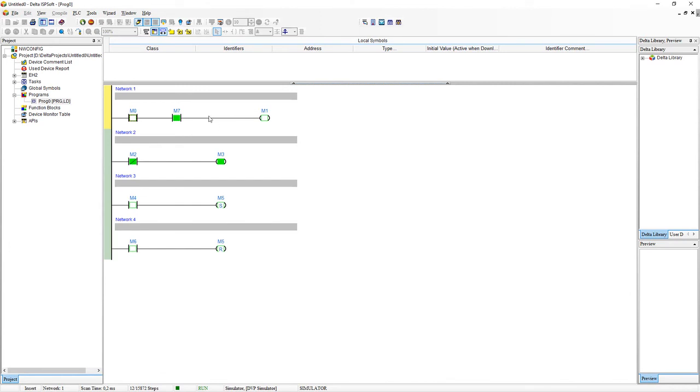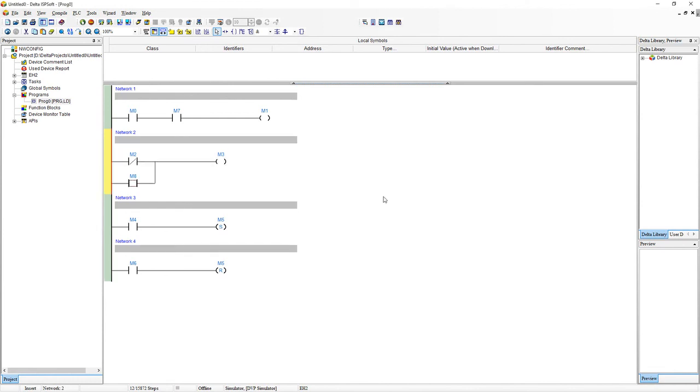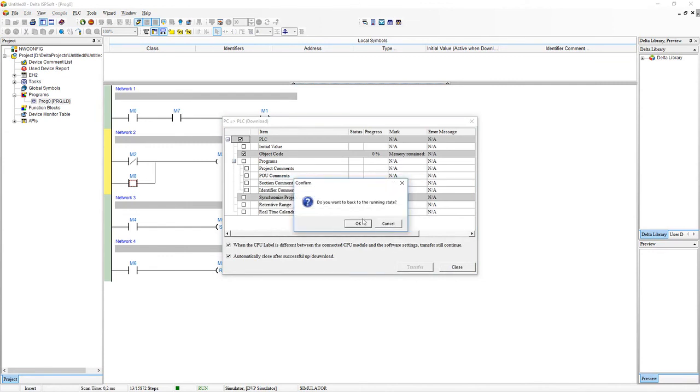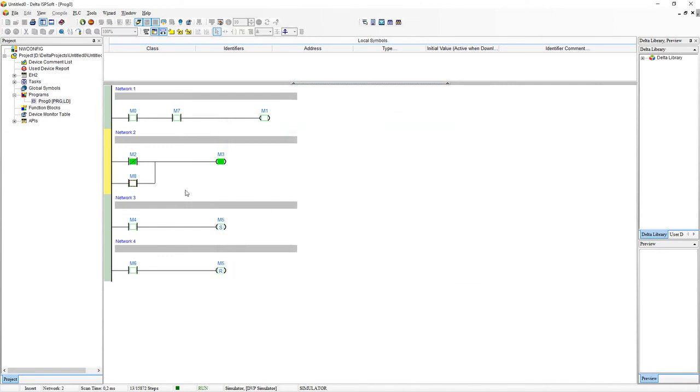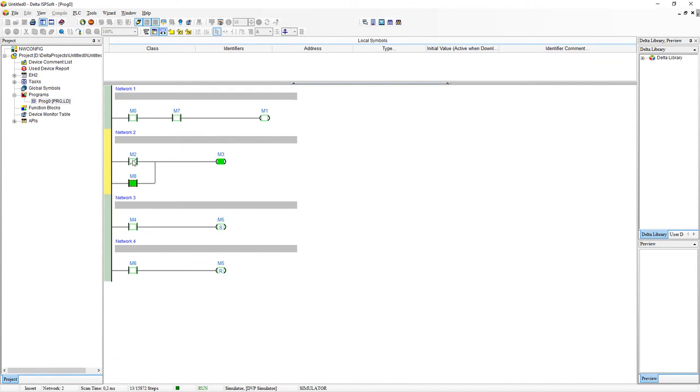And for your electrical guys once again no current can flow because there is no current basically at this source or if this one is off and M1 is on current also can't flow through to M1. So some other things you can also do is you could do for example an OR M8. Add that in and click it into online mode just to show you what it does. So you'll see that M3 is now on but let's turn this to on so that M3 is not energized and M8 turn that on. So basically if M2 or M8 condition is met M3 will turn on. So that is how you can chain different bits in a rung or use them in parallel and then do certain logic with it. And this makes it really useful because you can get specificity on all your functions and your logic that you want to do.